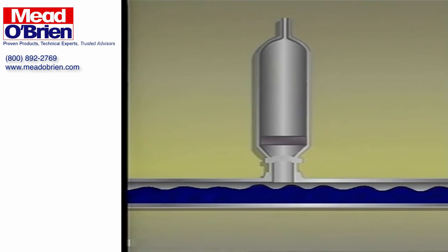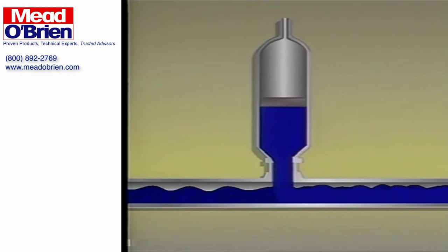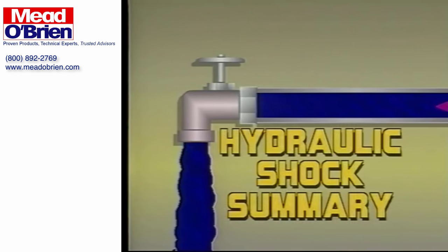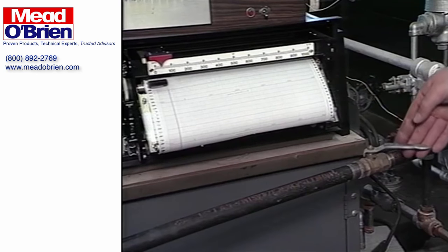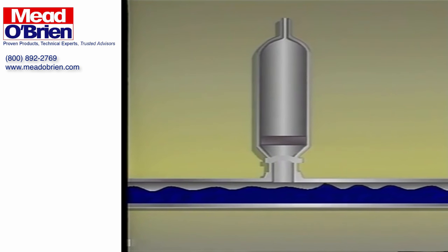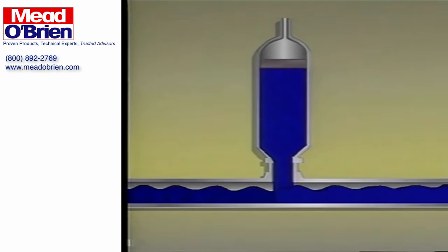Water hammer arrestors, if correctly sized, placed, and maintained, will reduce water hammer. When the forward motion of the water column is stopped by the valve, part of the reversing column is forced into the water hammer arrestor. The water chamber of the arrestor expands at a rate controlled by the pressure chamber, gradually slowing the column and preventing hydraulic shock. To prevent water hammer due to hydraulic shock: avoid suddenly stopping water columns, ensure slow closure of valves, install spring-loaded center-guided non-slam or silent check valves that close before flow reversal, and use water hammer arrestors if necessary — ensuring they are sized and placed correctly and well maintained.